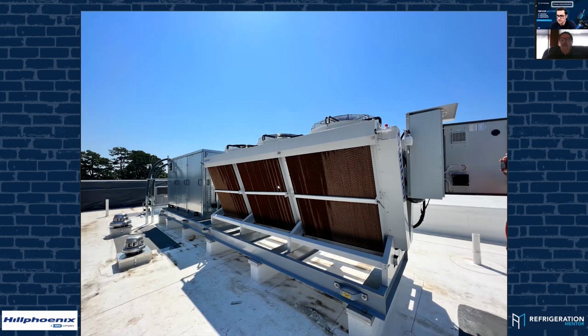They do. They actually measure the water flow using the water meter in line with the Belimo. Awesome. That's perfect. So a couple other options that Güntner has is you can set it up to what they call an LCCM feature. And what that'll do is, as the fans are ramping down when it gets a cooler ambient, instead of them ramping down to 0, it'll actually start stepping fans off.